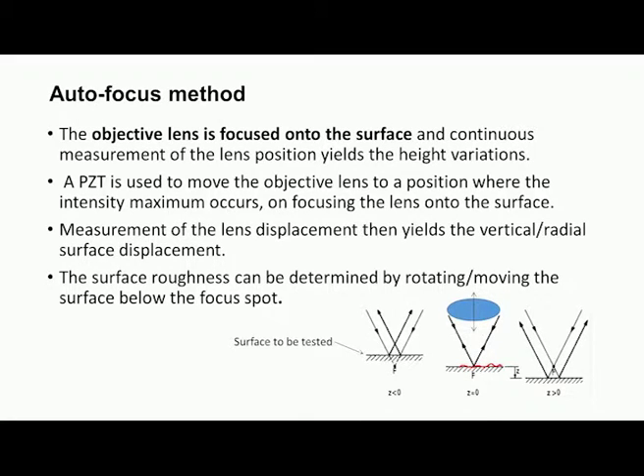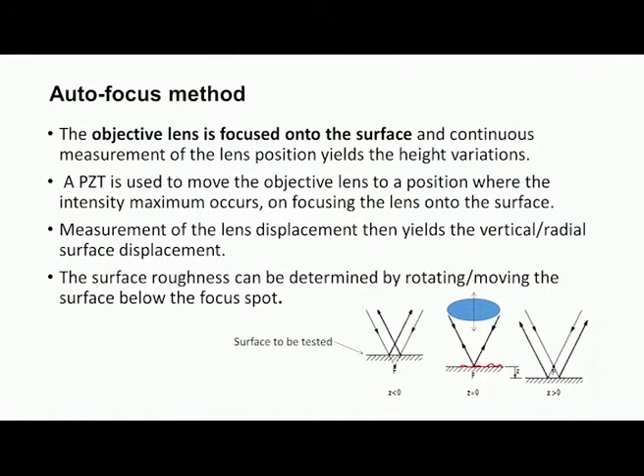So, in order to focus the light onto a particular point on the surface, we need to move the objective lens using PZT. The measurement of lens displacement, by what amount the lens moves up and down, yields the vertical or radial surface displacement, and the surface roughness can be determined by rotating or moving the surface below the focus spot.